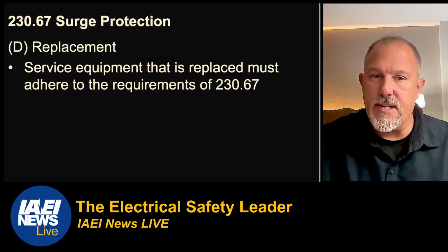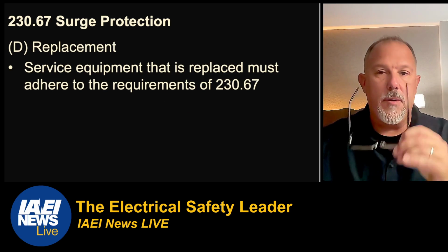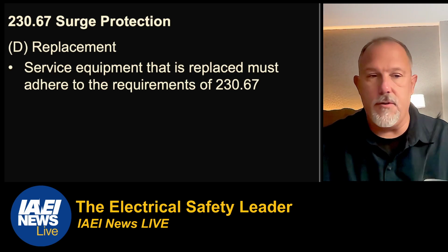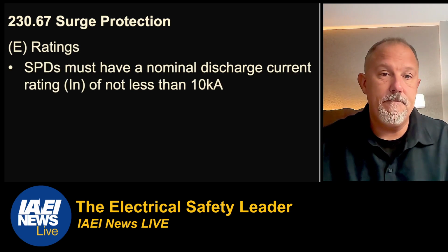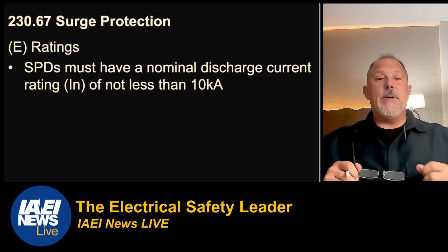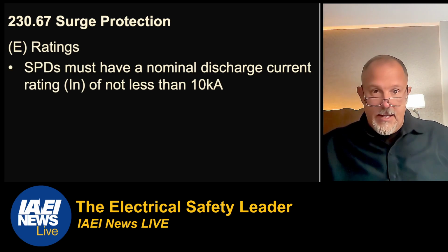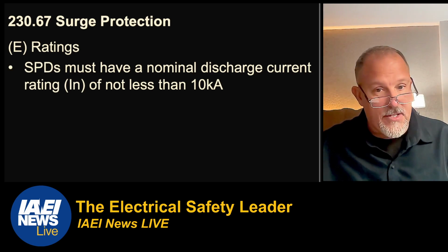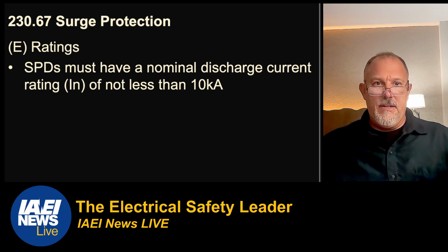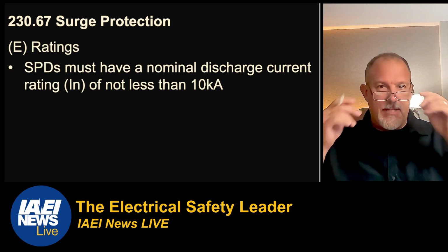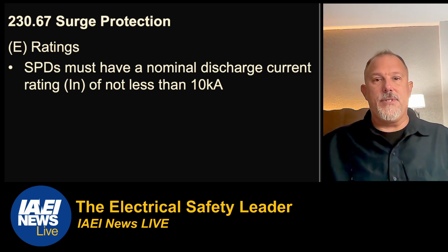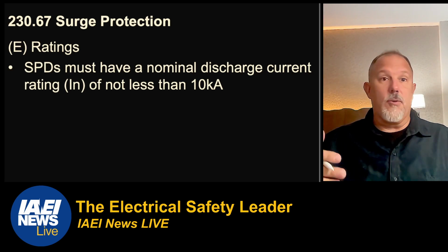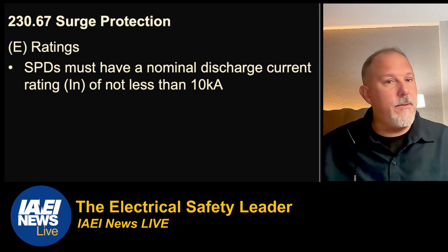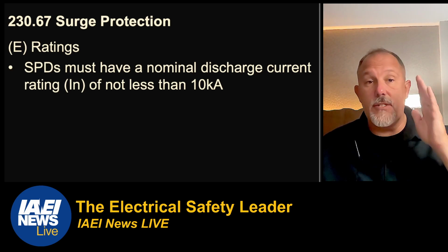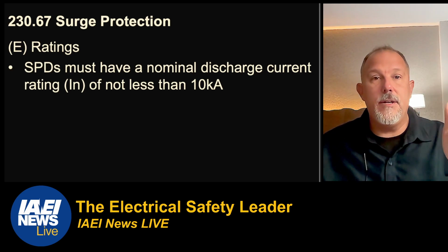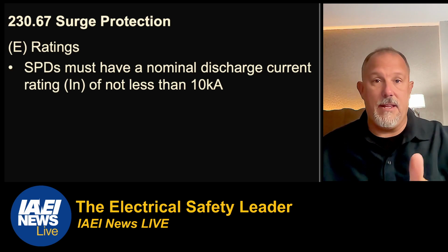You can put a type 1 or a type 2, and if the service equipment is replaced, you have to follow the rules, so you're going to be putting surge in. And then the ratings. SPDs must have a nominal discharge current rating of not less than 10,000 amps. I don't know why some people feel that our electricians out there are going to get confused and think that is an interrupting rating or a withstand rating. Nope, this is different. This is just a nominal discharge current rating of 10,000 amps.